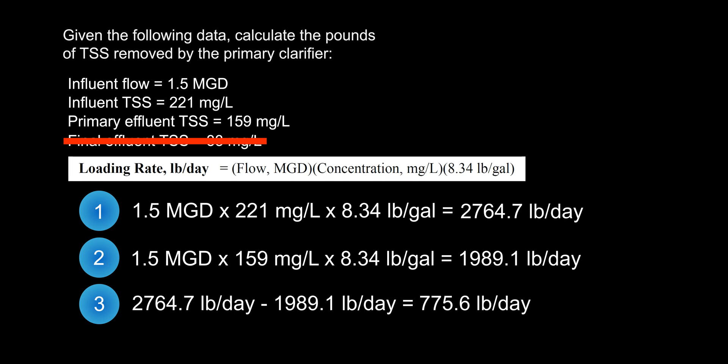This gives us our final answer of 775.6 pounds per day being removed by the primary clarifier, which is answer B. On a side note, we can see this primary clarifier is not performing well, with a removal rate of about 28%. A primary clarifier without additional chemical treatment should be removing at least 40–60% of TSS. This is why performing these tests and equations is vital to troubleshooting a treatment plant.